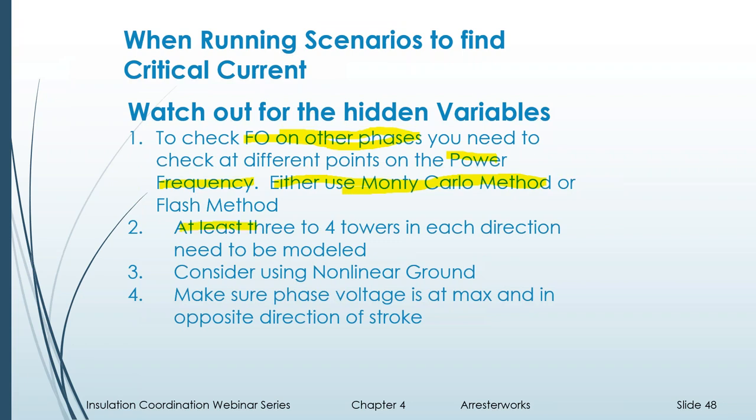I always test at least 3 or 4 towers in each direction. Beyond that you can, but you'll find that usually nothing happens that far out. Even in a third tower away, it's rare to have anything happen in either direction. So the fourth tower catches it all.